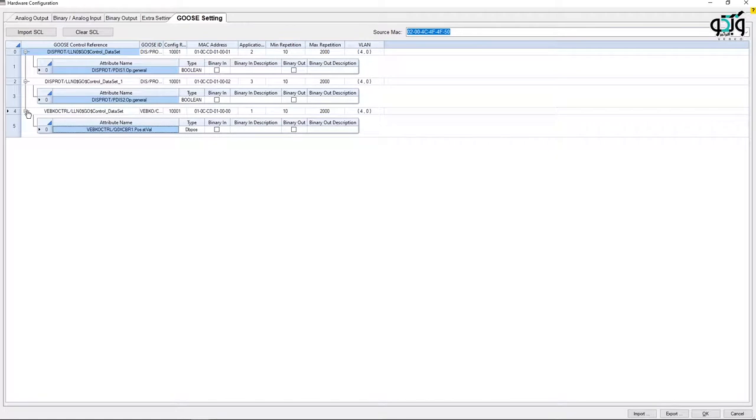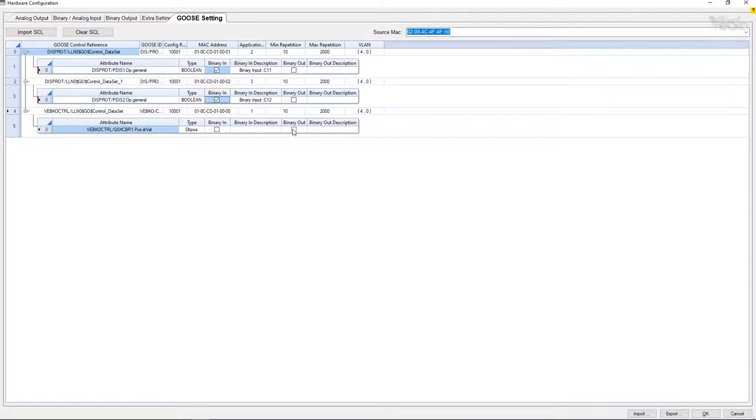If your selected option is put in the relay's output list while you want it in the input list, you can simply choose binary in option. Conversely, if the tester is supposed to excite the input of the relay, you can select binary out after choosing the desired option.